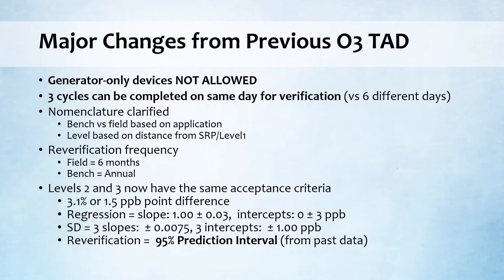Finally, levels two and three now have the same acceptance criteria, which is 3.1% or 1.5 ppb point difference. For the regression, the slope needs to be 1 ± 0.03, the intercept ± 3 ppb. The standard deviation of the three slopes is required to be ± 0.0075, and the three intercepts ± 1 ppb.